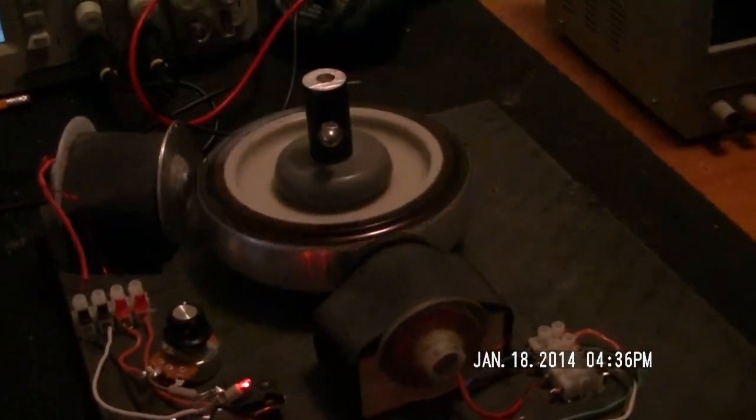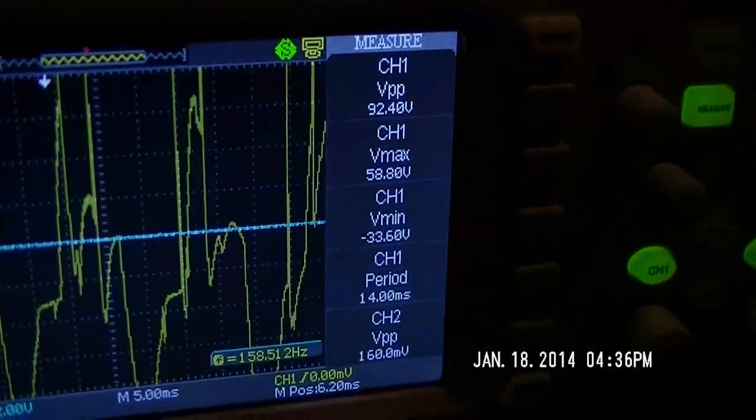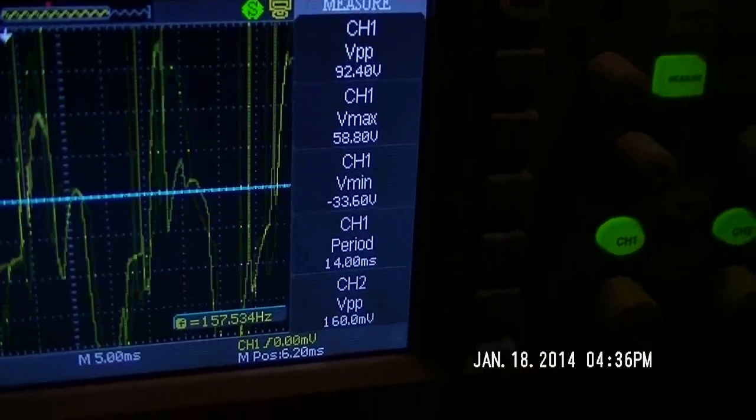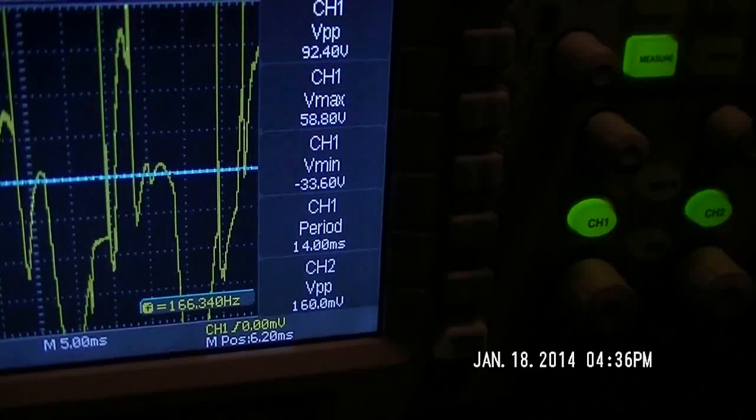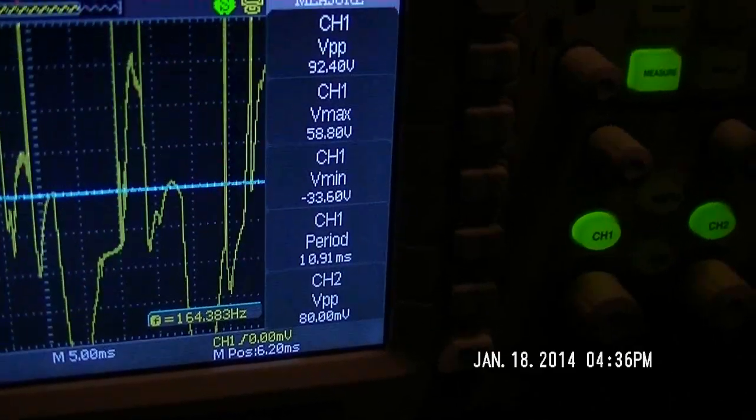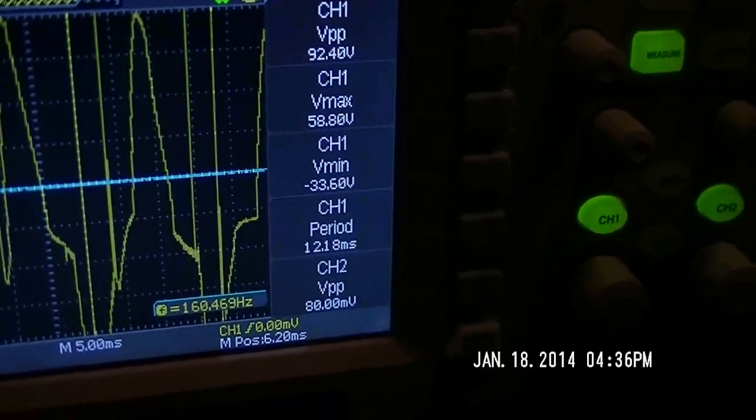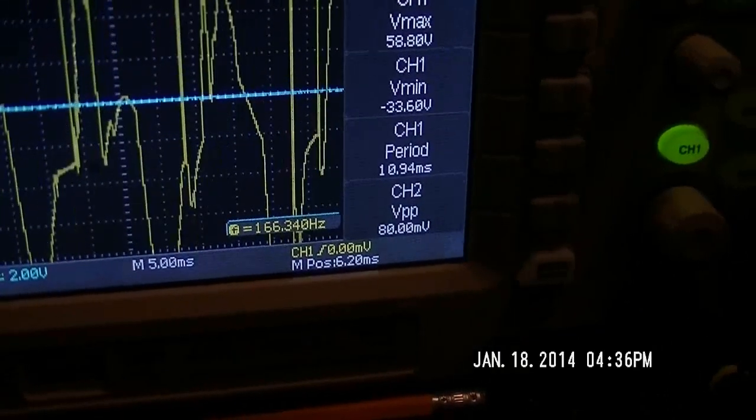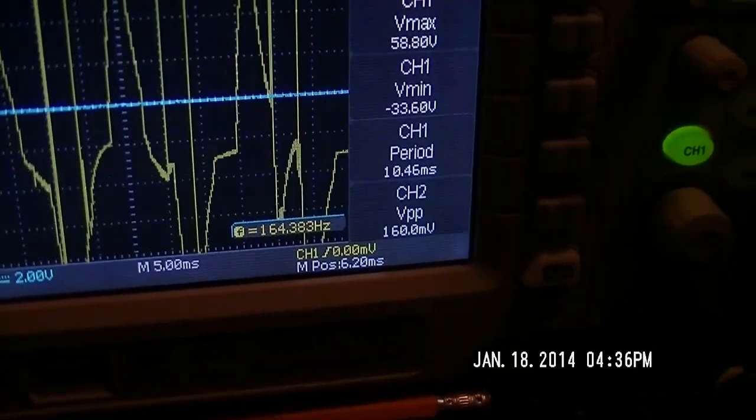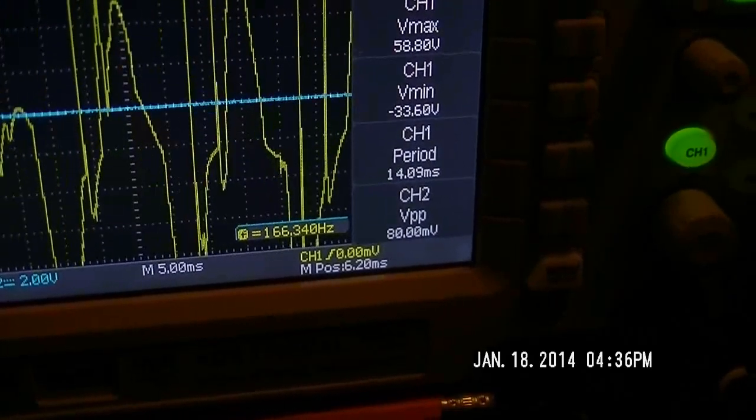It's fluctuating a little bit. This is making, sorry for the camera, it's making a plus 58.8 and minus 33.6, so it has a peak to peak of 92.4 and it's fluctuating 160 to 166 Hertz.